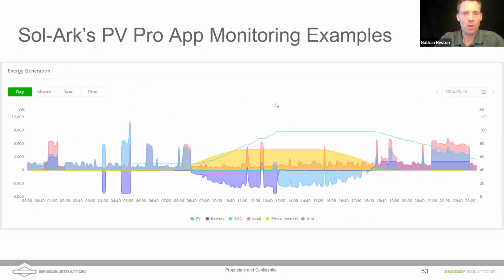That's awesome. We're looking at an AC coupled system here. This is an example where you can see the PV come on during the day. You've got micro inverters there, that's the AC coupling I was talking about. This is a system where the customer is trying to do self-consumption and time of use. As micro inverters come on, you'll see that battery percentage start to increase. That battery percentage gets saturated, and then that solar continues to power the loads in the home. So there's very little import from the grid in this type of system.